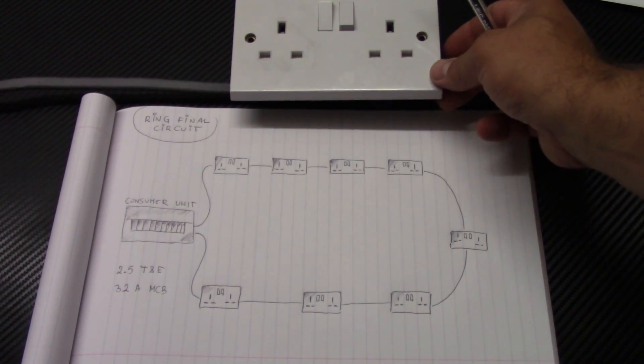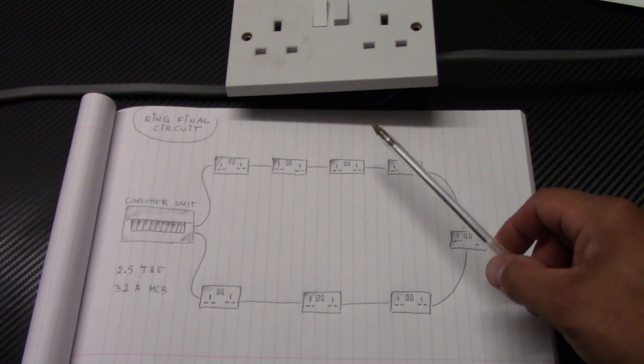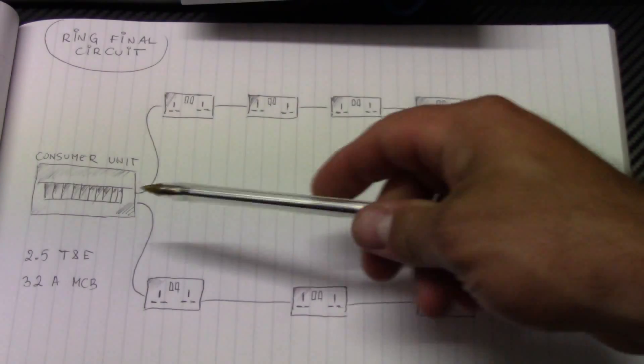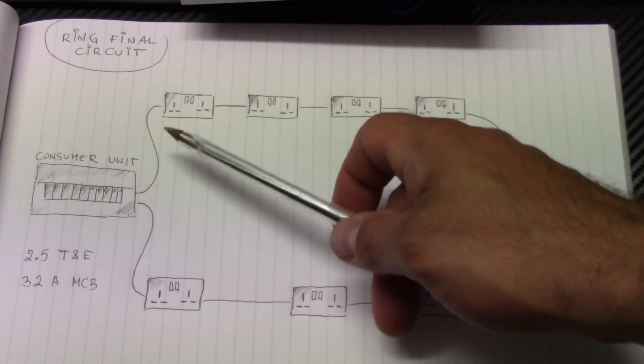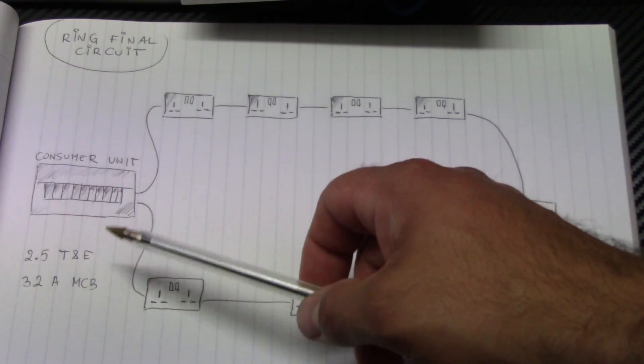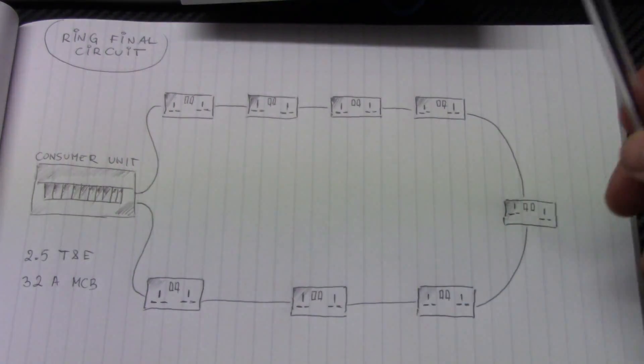But before I show you the wiring, I just want to quickly explain how the ring final circuits are connected. The cable used in ring final circuits is 2.5 twin and earth and is protected by 32 amp MCB at the consumer unit.